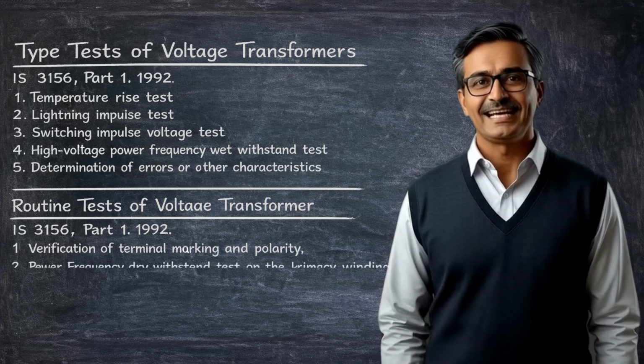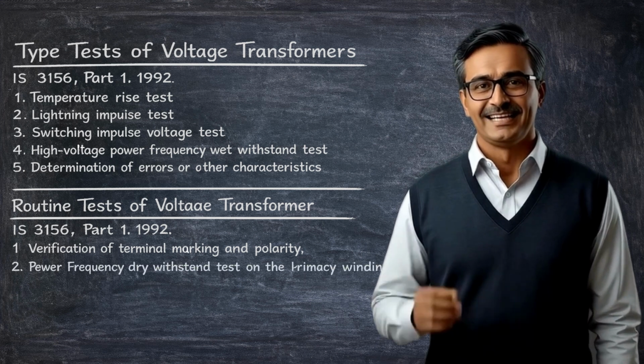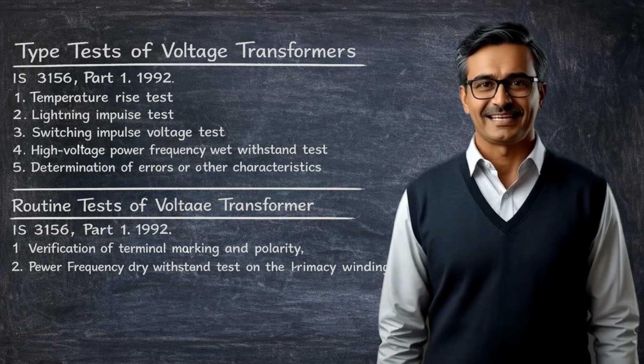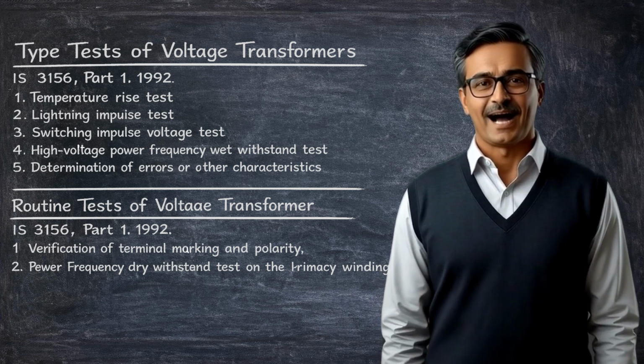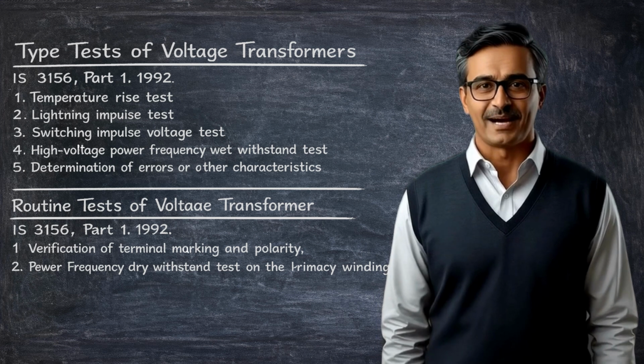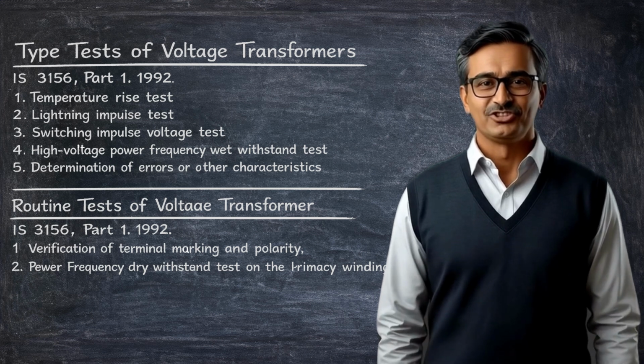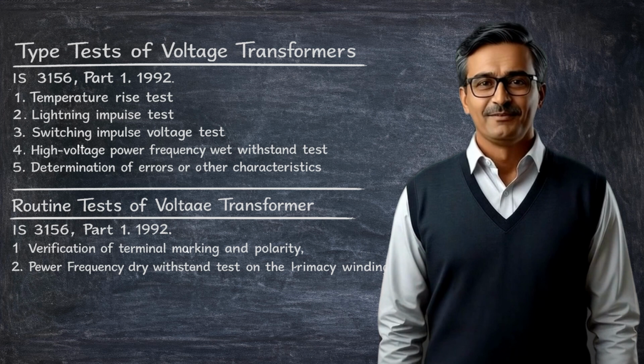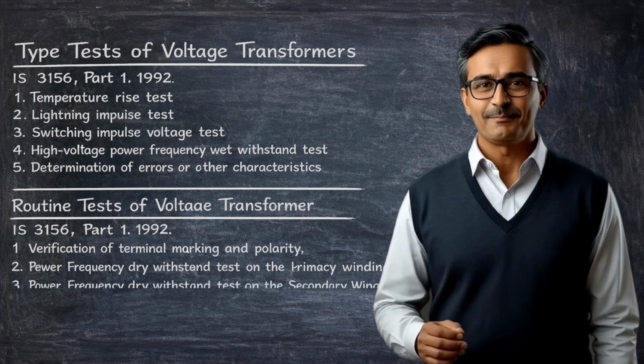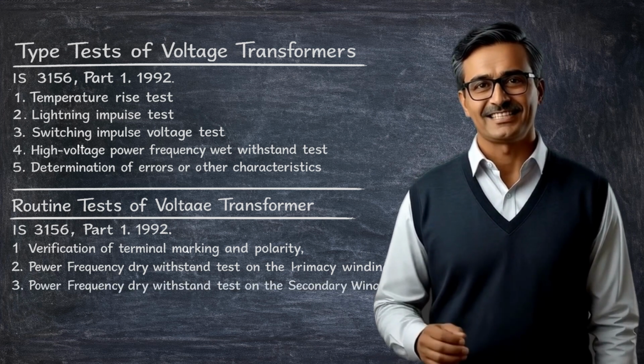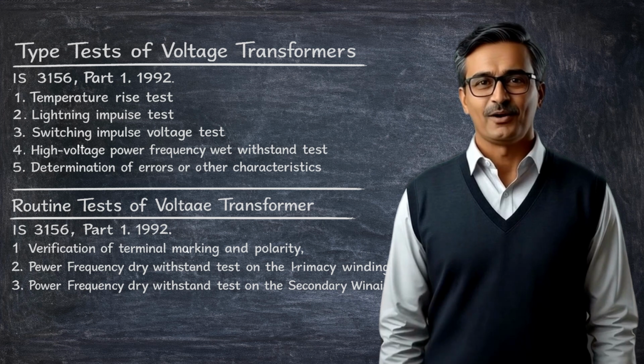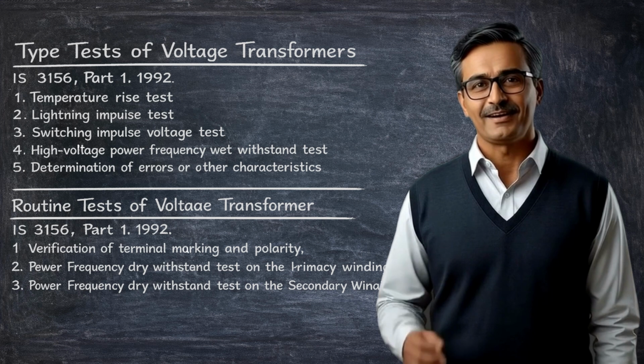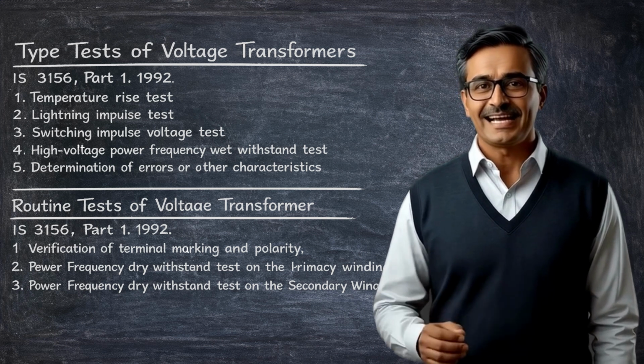The second test is the power frequency dry withstand test on the primary winding. In this test, we apply a specified high voltage at power frequency to the primary winding. The purpose is to check the insulation strength of the primary winding. The third test is the power frequency dry withstand test on the secondary winding. Here also, a specified voltage is applied to the secondary winding to verify the insulation capability of the secondary circuit.